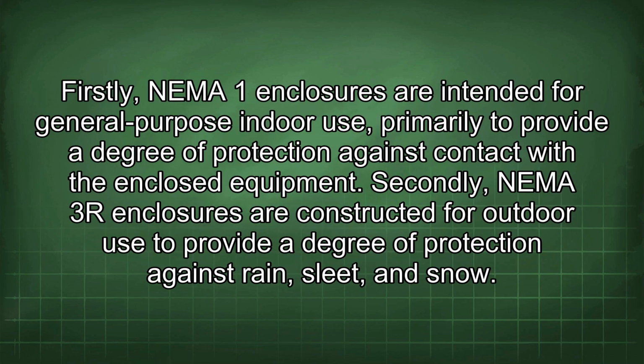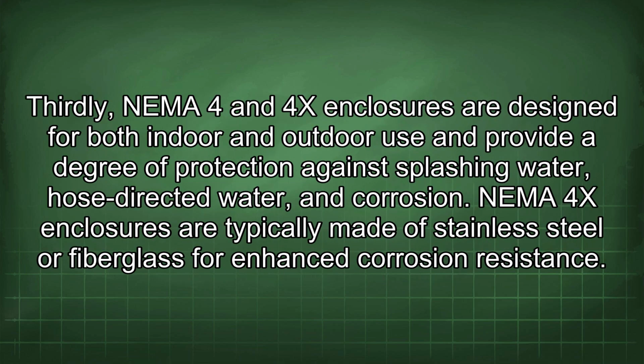Firstly, NEMA 1 enclosures are intended for general-purpose indoor use, primarily to provide a degree of protection against contact with the enclosed equipment. Secondly, NEMA 3R enclosures are constructed for outdoor use to provide a degree of protection against rain, sleet, and snow. Thirdly, NEMA 4 and 4X enclosures are designed for both indoor and outdoor use and provide a degree of protection against splashing water, hose-directed water, and corrosion. NEMA 4X enclosures are typically made of stainless steel or fiberglass for enhanced corrosion resistance.